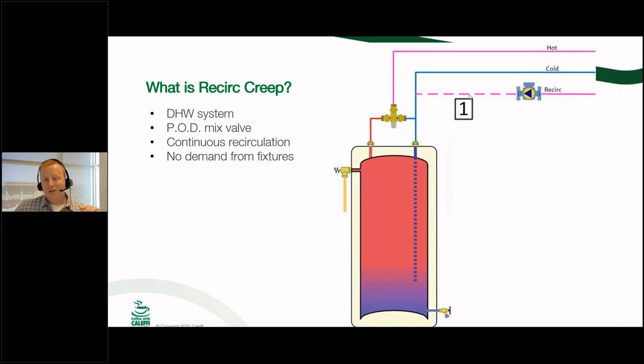But if that recirc is sized properly, balanced properly, and everything like that, you're typically going to be seeing about a 5 to 10 degree temperature difference on the recirc coming back versus the mixed outlet going out to that building. So just for round numbers, say you're distributing 120 and you're getting roughly 110 to 115 coming back. And what you're going to have here is that recirc's coming back, and now it has the ability to either go into the cold inlet of the mixing valve or down through your domestic hot water source and then back to the hot inlet of the mixing valve.